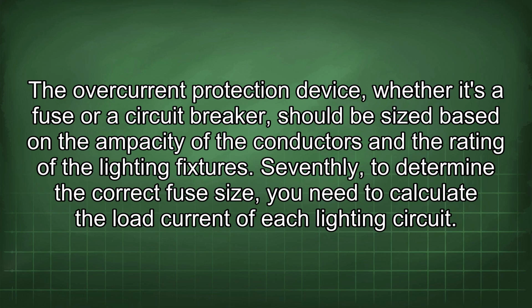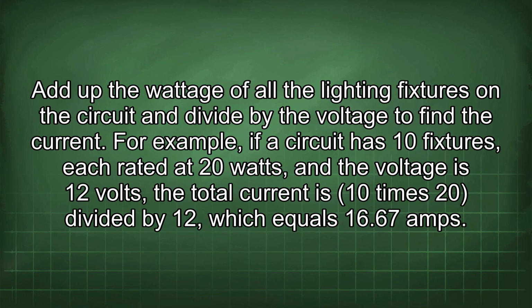Seventhly, to determine the correct fuse size, you need to calculate the load current of each lighting circuit. Add up the wattage of all the lighting fixtures on the circuit and divide by the voltage to find the current. For example, if a circuit has 10 fixtures, each rated at 20 watts, and the voltage is 12 volts, the total current is 10 times 20 divided by 12, which equals 16.67 amps.